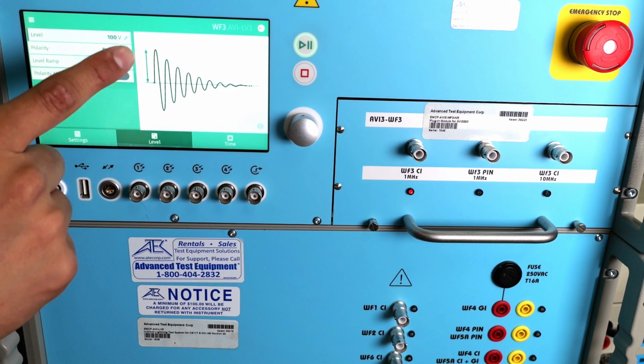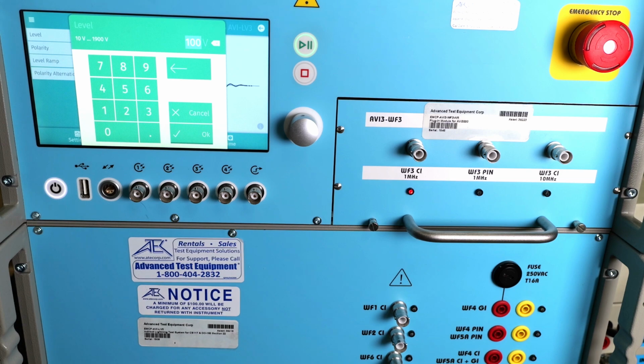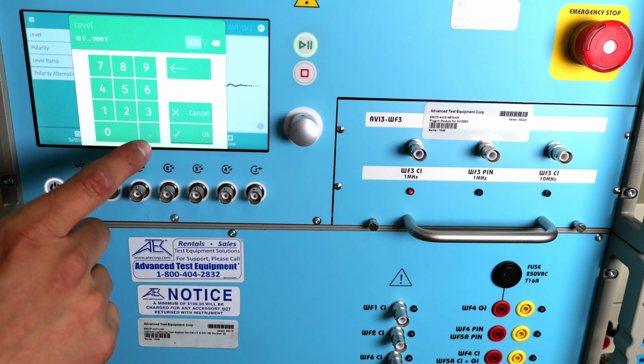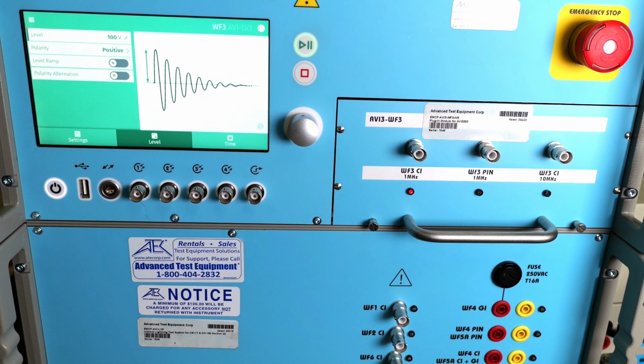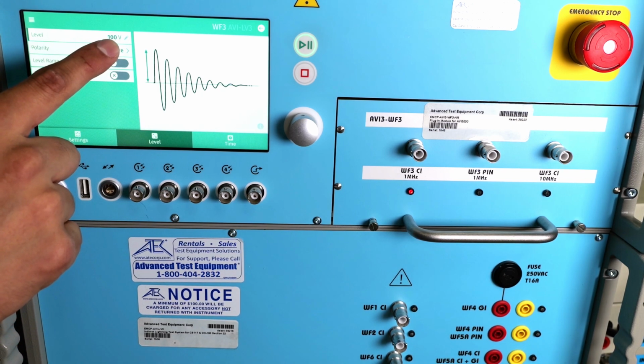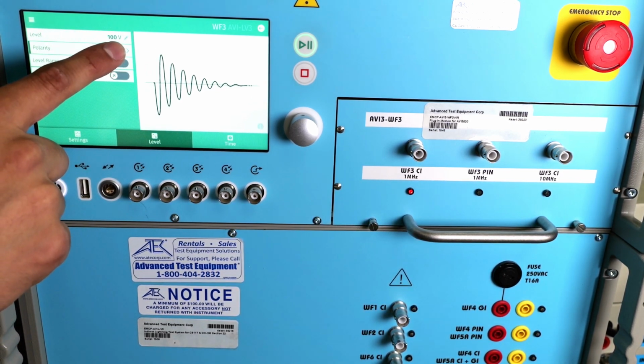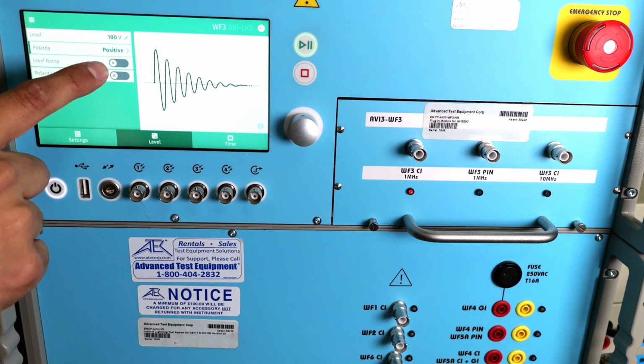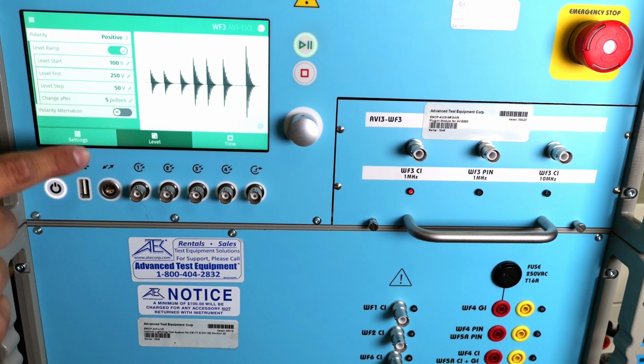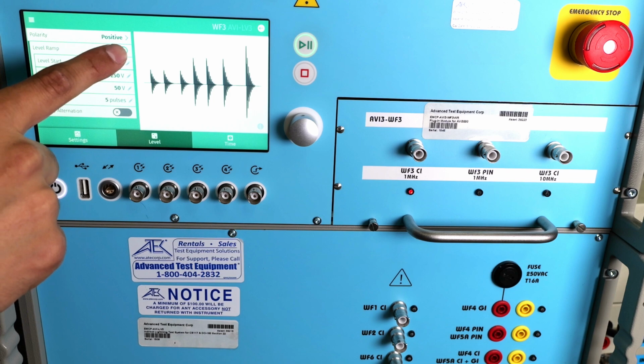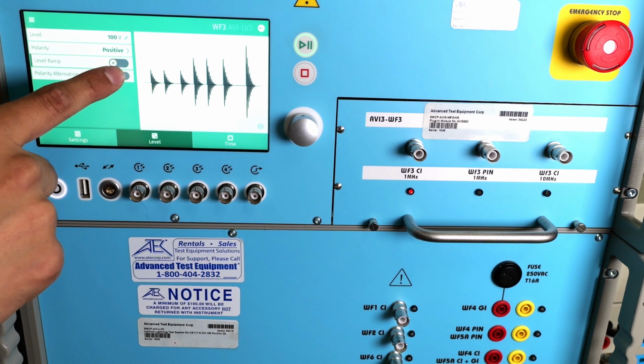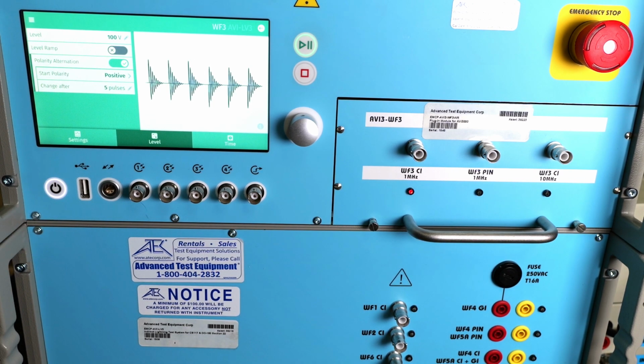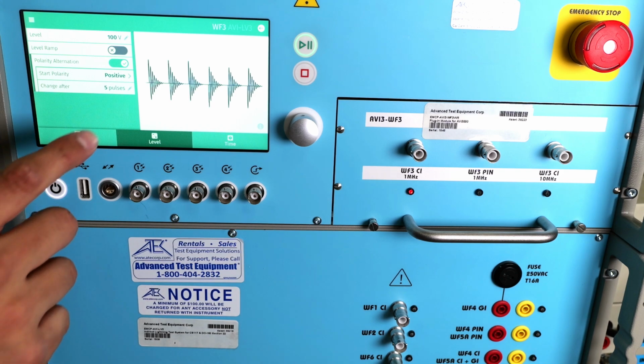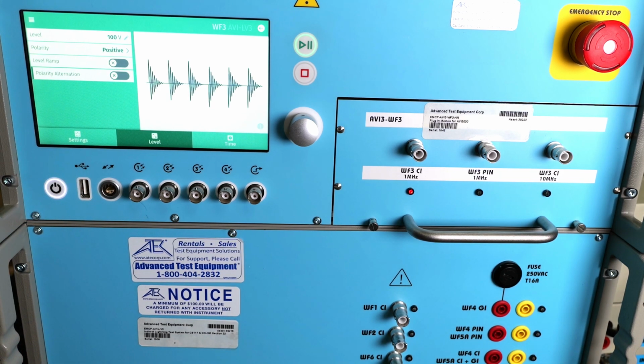Within the generator, I could select the level on this particular waveform in this induction method from 10 volts up to 1900 volts. But for my demonstration today, I'm going to keep it at 100 volts. And I could change the polarity from positive to negative, and it will update the display there. You could change the level ramps to increase or decrease the voltage. And you can also alternate the polarity, which I'm going to take off here.